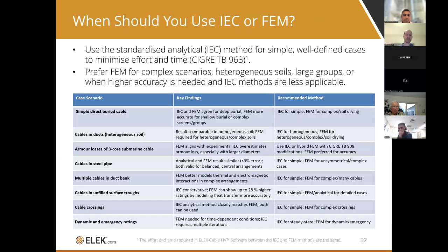So this is an interesting topic. We often get asked, when should I use IEC as opposed to FEM? And as we've seen, why would you use it if the cable ampacity is going to be calculated as lower? Now that depends on your perspective, right? Sometimes if you're a contractor or a consultant, perhaps you want to get as much cable ampacity out of your cables as possible in terms of the model.